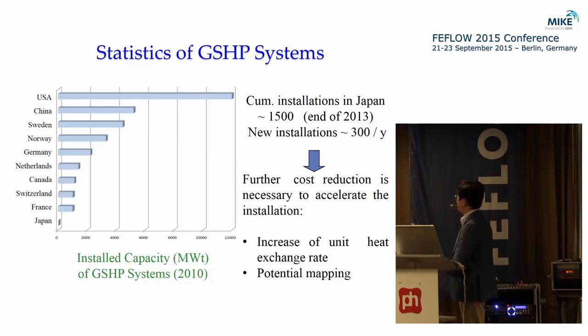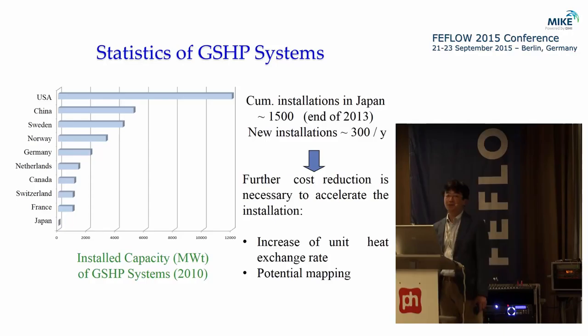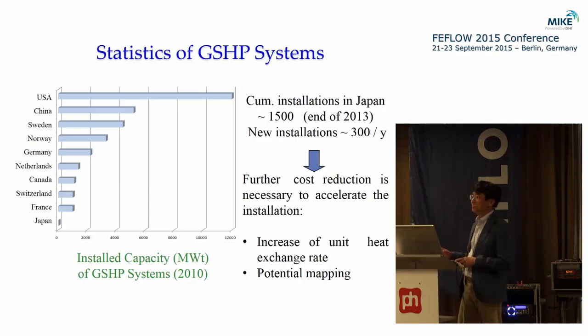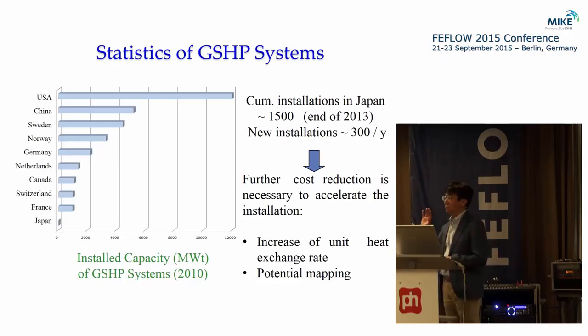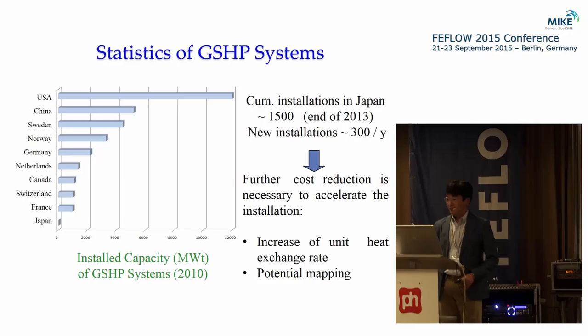For the wider installation of the system, the important factor is to increase the unit heat exchanger rate — in other words, to minimize the heat exchanger length. The heat extraction rate from the ground heat exchanger is strongly dependent on the thermophysical properties in the ground and also the velocity of groundwater flow. These factors strongly depend on the installation point; it differs location to location. Another good procedure to promote installation is to develop a potential map showing the suitability of ground source heat pump systems.